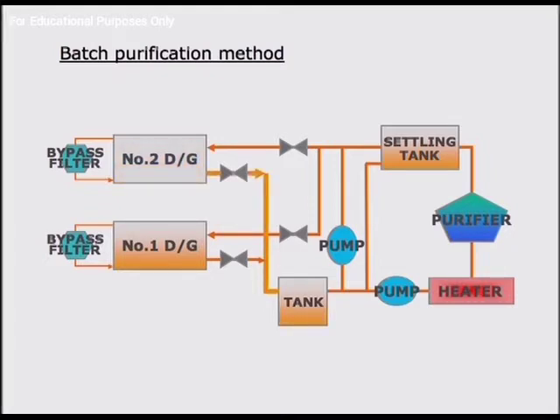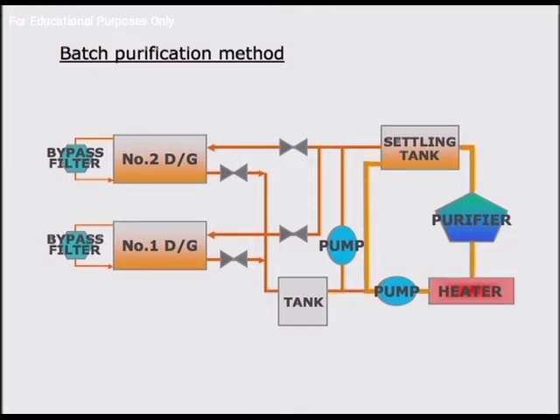For example, transfer the lube oil of number two diesel engine generator to the tank, then let the already cleaned lube oil flow to number two diesel engine generator. Transfer the used lube oil to the settling tank in preparation for the next replacement. Conduct the cleaning treatment for the used lube oil, setting the cleaning time such that the lube oil of the settling tank flows through the purifier 20 times or more.